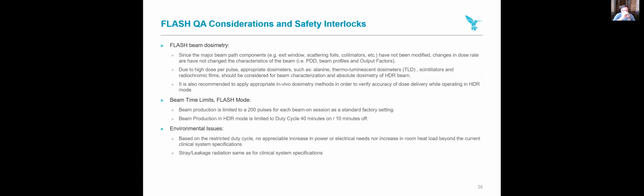So what QA and safety interlock considerations do we have in this current incarnation of the system? With the FLASH beam dosimetry, it hasn't really been modified. The exit window, scattering foils, and collimators have not been modified. So changes in the dose rate don't really change the PDD, the beam profiles, and output factors. That's what we're seeing in measurements, and now our customers are seeing that as they do their own independent measurements. At this high dose per pulse, you have to really look at appropriate dosimeters. The monitor chambers inside the system that you use in conventional mode are just capped ion chambers. They saturate, and you can't really rely on them. So you've got to come up with other ways of doing this.